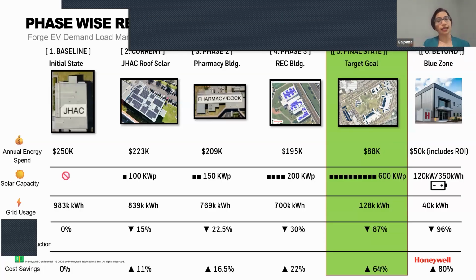When we calculated, we said we can bring down your energy spend a lot more if we put in a 120 kilowatt, 350 kilowatt hour battery. Remember the graph showing how you could shift some load later into the evening, or discharge the battery around peak time? The big dollar savings really come from going back to the utility provider and renegotiating your capacity charges and maximum peak demand. If the customer isn't utilizing that high curve of maximum peak demand, bringing that curve down sends thousands, even hundreds of thousands of dollars back to the customer's pocket.